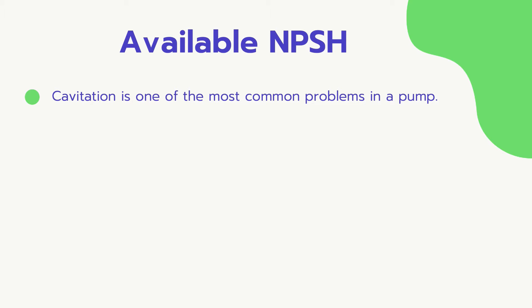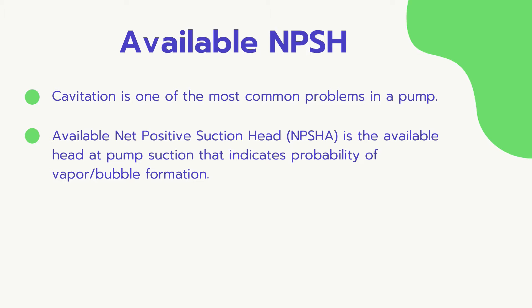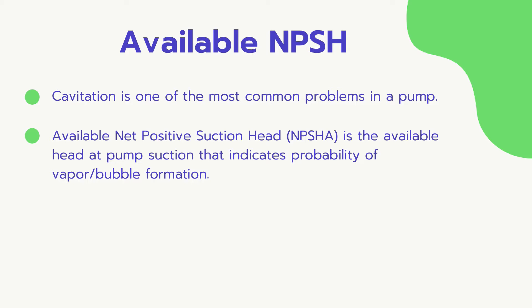So what is the available NPSH, or NPSHA? The available NPSH is the available head at pump suction that indicates the probability of vapor or bubble formation. This means that if the NPSHA is enough, then cavitation shouldn't occur and the pump can work efficiently. But if it is too low, this can cause cavitation, which can lead to severe pump damage if the pump works for some time.